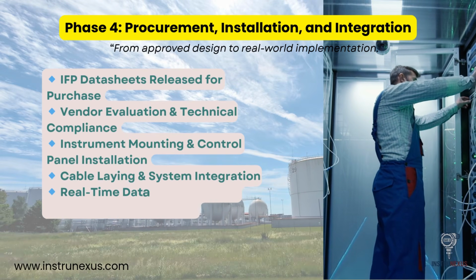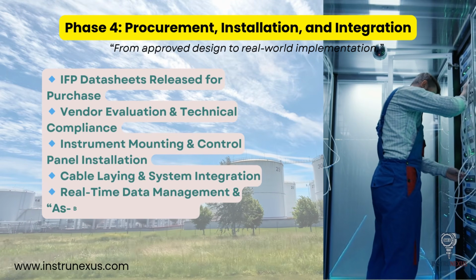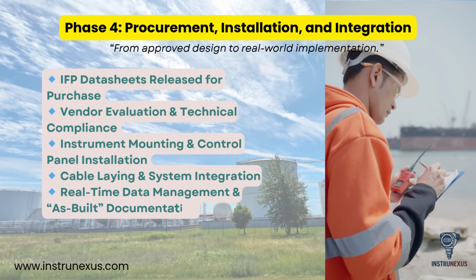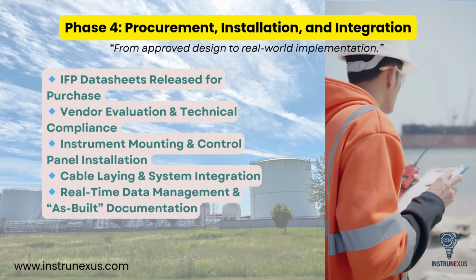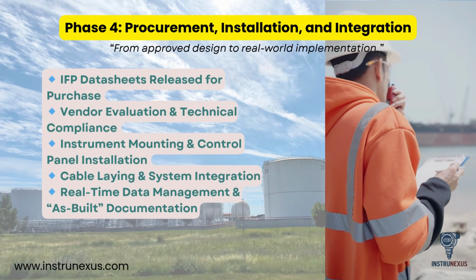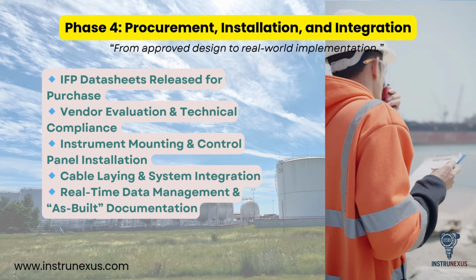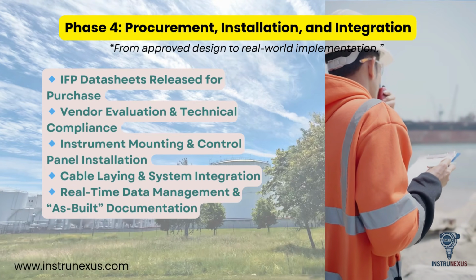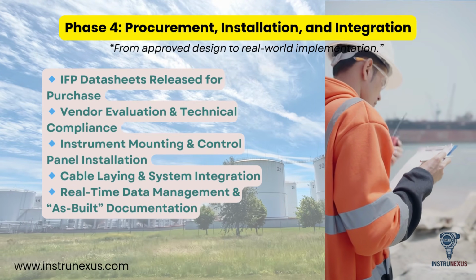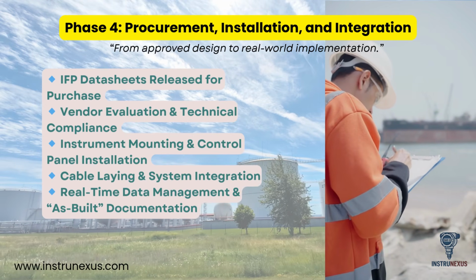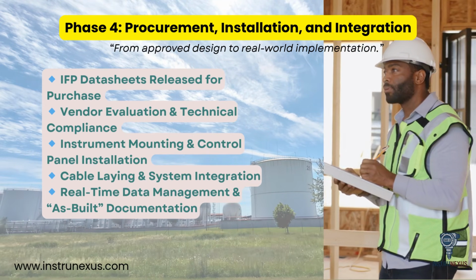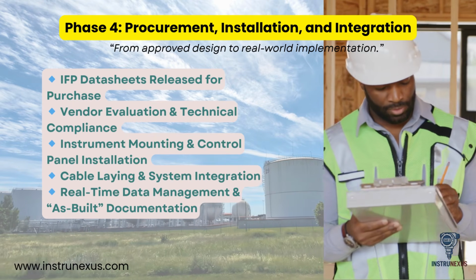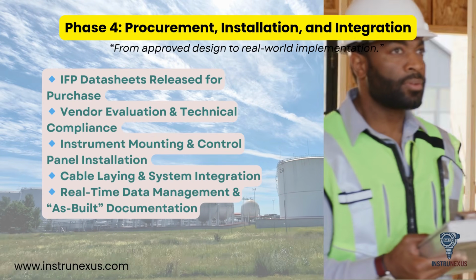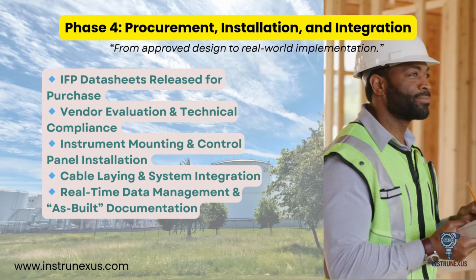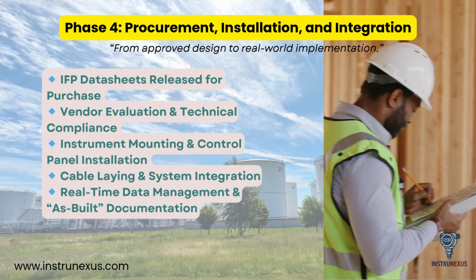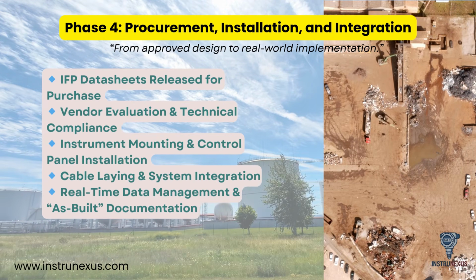Instruments are mounted, control panels installed, and kilometers of cabling laid to connect field devices with the control system and communication networks. During this phase, data management and traceability become critical. Every physical change, configuration update, and cable termination is documented in real time, forming the foundation for as-built records, the definitive reference for future maintenance, troubleshooting, and system upgrades. This marks the transition from design on paper to control in action.